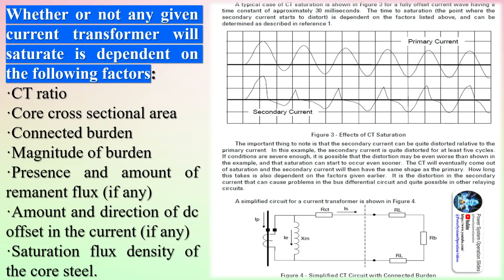An ideal differential relaying system takes advantage of the fact that the sum of the currents will be zero for external faults or load flow, whereas the sum will be equal to the total fault current for internal faults. Unfortunately, there are problems introduced wherein the ideal cannot always be obtained, and steps must be taken to ensure that the differential relaying system works properly even under non-ideal conditions.